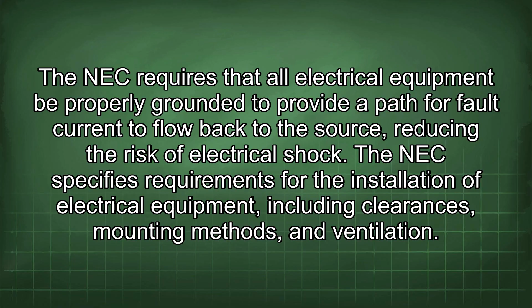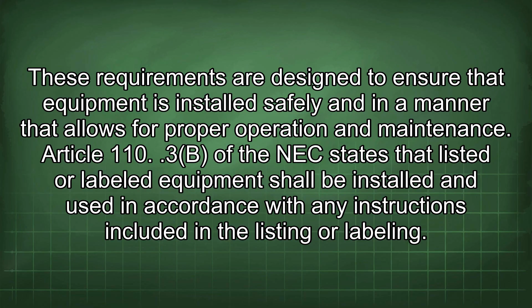The NEC specifies requirements for the installation of electrical equipment, including clearances, mounting methods, and ventilation. These requirements ensure that equipment is installed safely and in a manner that allows for proper operation and maintenance. Article 110.3(b) of the NEC states that listed or labeled equipment shall be installed and used in accordance with any instructions included in the listing or labeling.